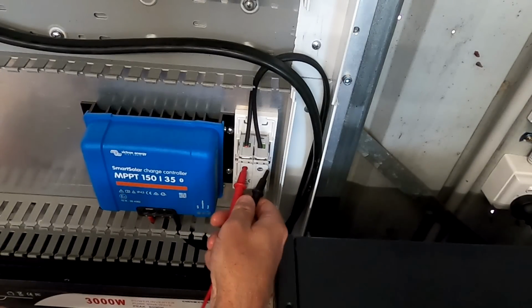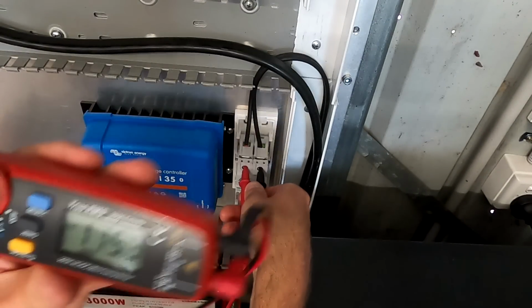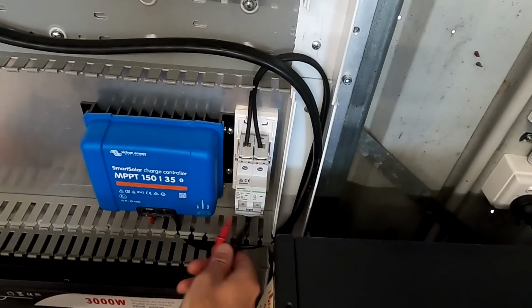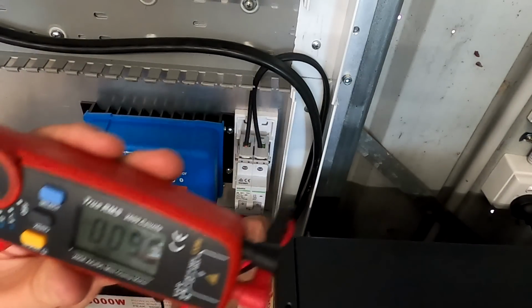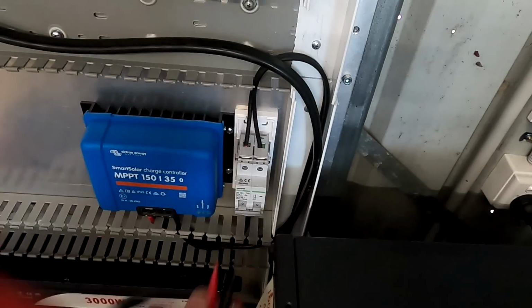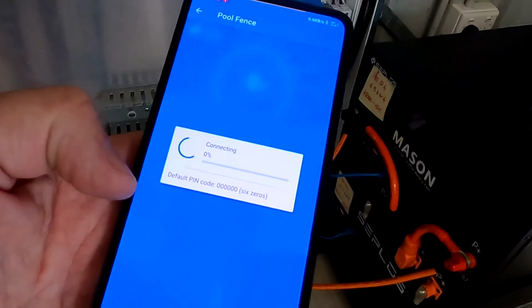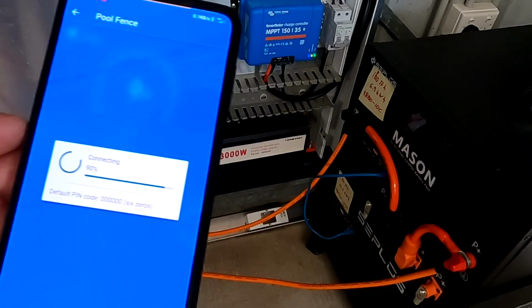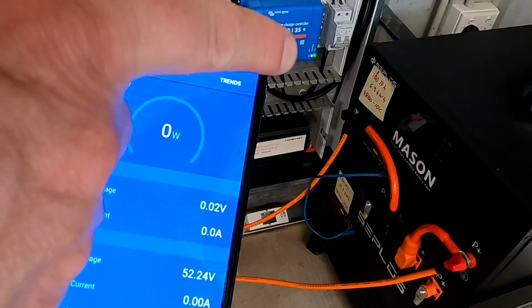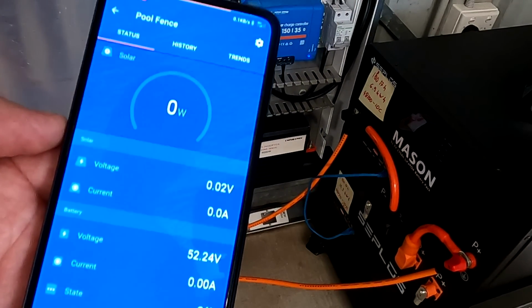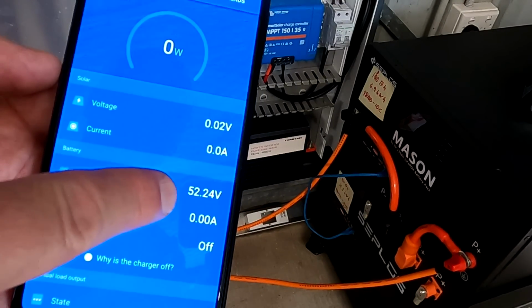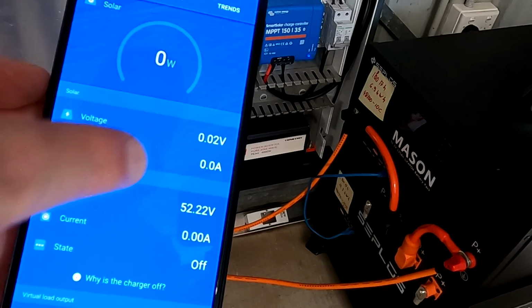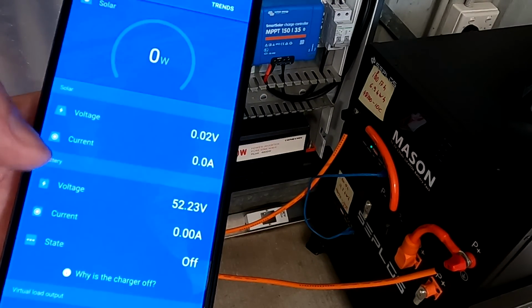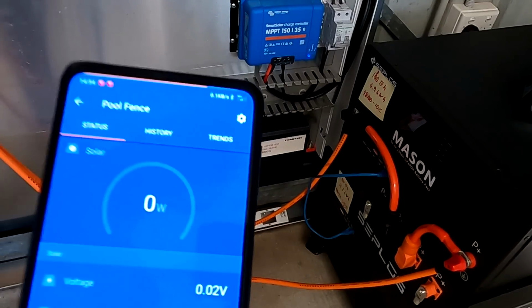I'm just checking the incoming solar for polarity. Yeah, that is positive. There should be nothing down here because the circuit breaker is still off. Okay, we click on the Pool Fence charge controller. It's flashing up there, connecting, and we can see the battery voltage 52.2 volts. No solar incoming. Let's change that.